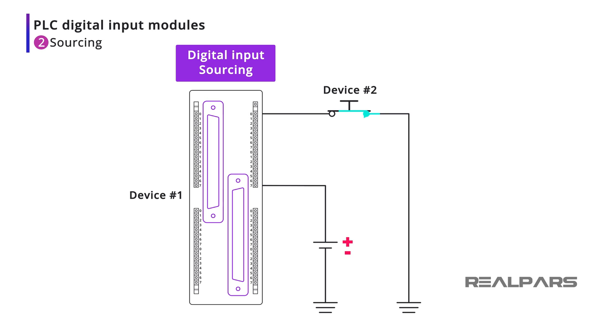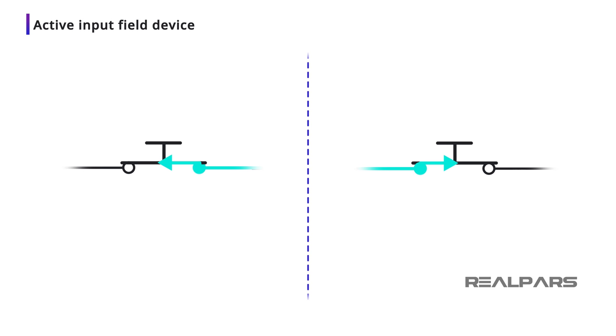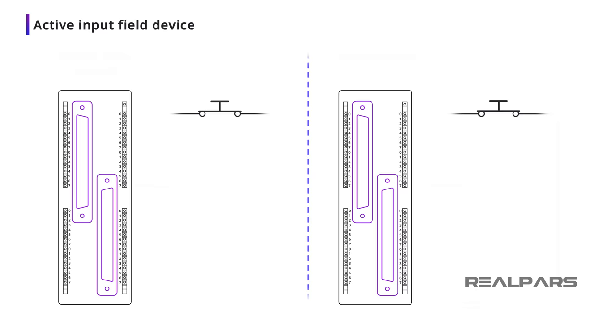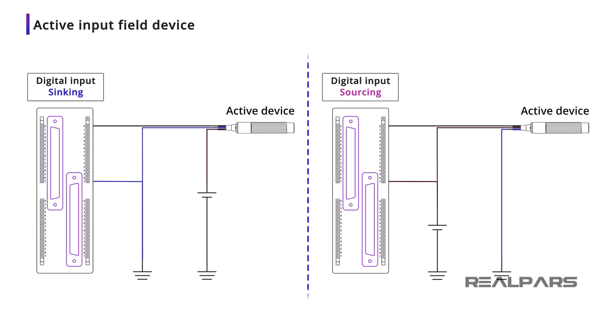Current can flow in either direction through a push-button switch because it is a passive device and not polarity dependent. There are many active digital input devices used in industry today that are polarity dependent — they must be wired correctly or they will not work at all. These active devices will be labeled as either sinking or sourcing. You can learn more about active sensors in our other videos, and we'll direct you there at the end of this video.